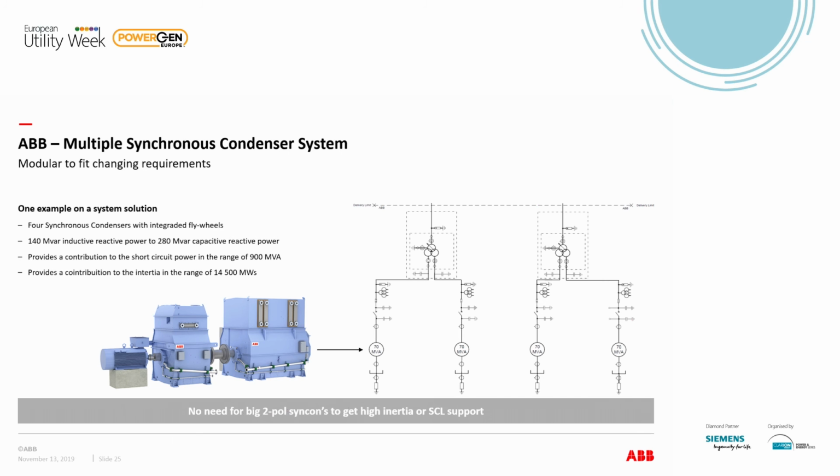In reality, this would be a good way if you have the possibility to measure your inertia. Maybe you don't need a big unit the whole time. You may switch in the modular system when the inertia is required, and not just because you only have the big unit. So a combination of modular systems with continuous measurement of inertia, which is offered on the market today, would be a nice combination, because then you can really optimize your assets.